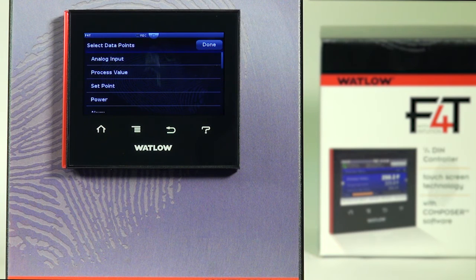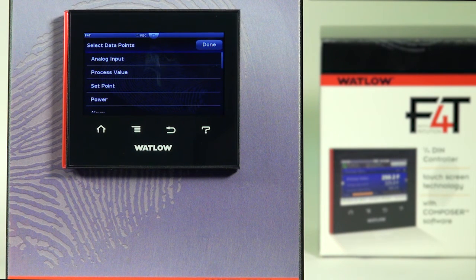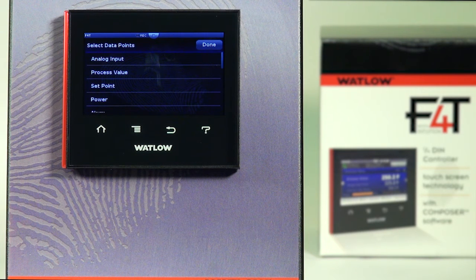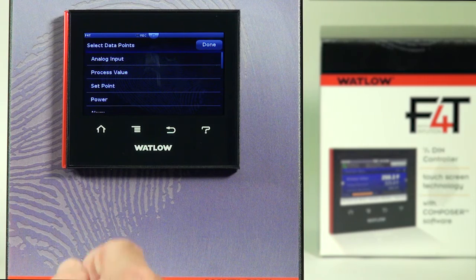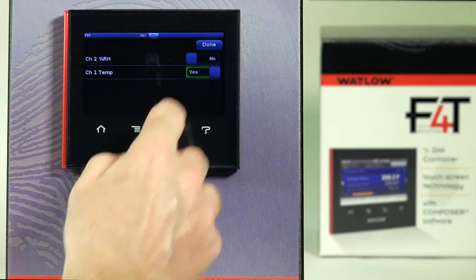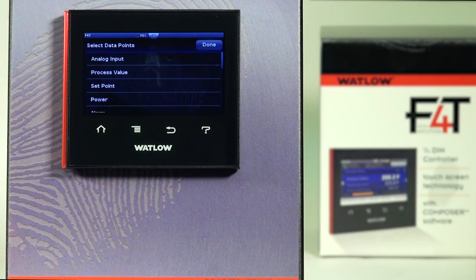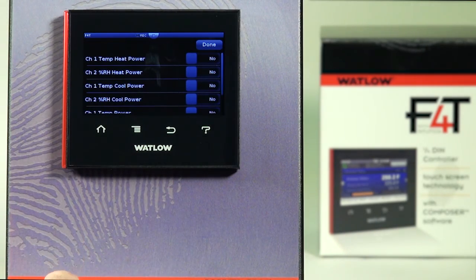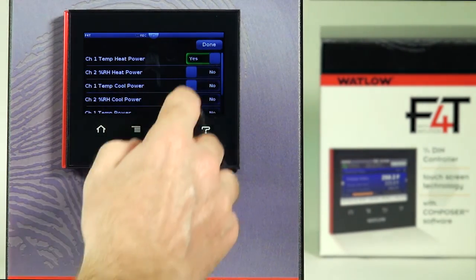Process values can be the same as analog inputs, or they could be a combination — for example, averaging two analog inputs as the process output value. For wet/dry bulb humidity, you could have one analog input for temperature, another as the wet bulb, and the output of that process value be in percent RH. I've already picked the sensor for channel one temp, so now I'll continue with the set point and then the heat percent power. Channel one temp heat power — press done.